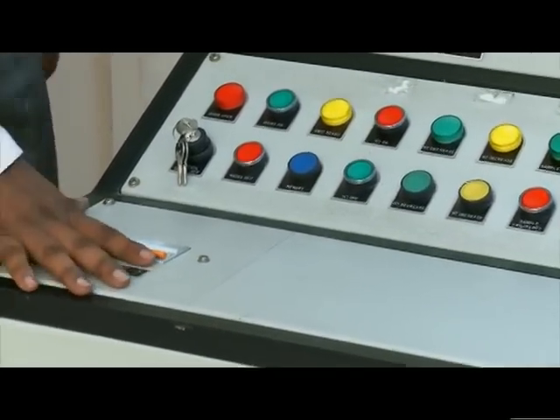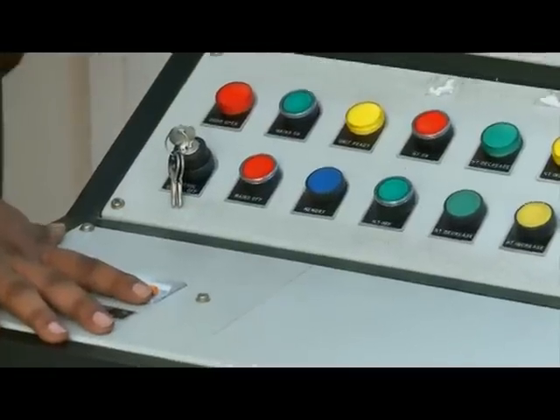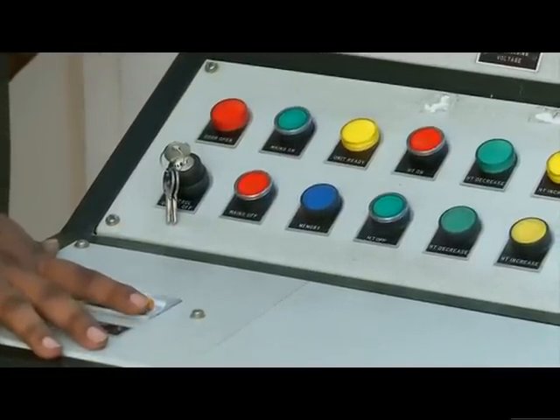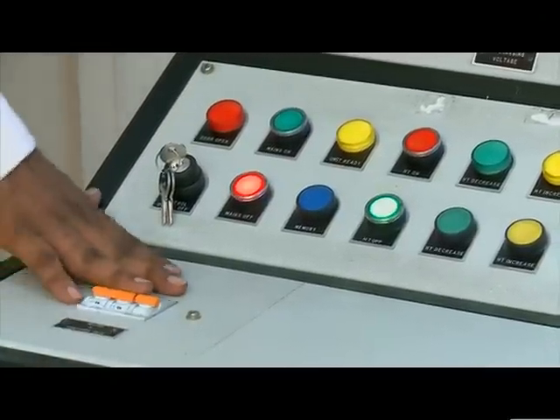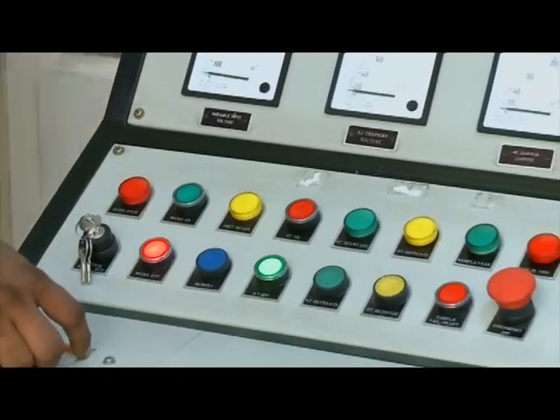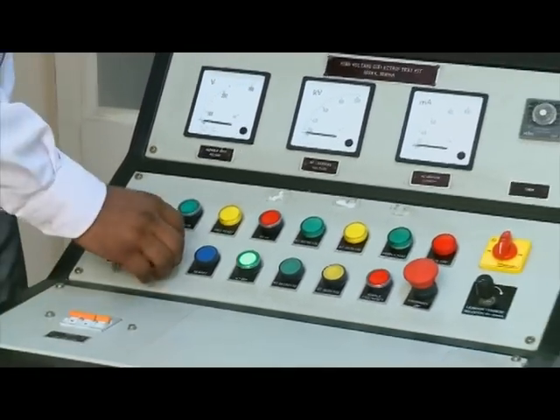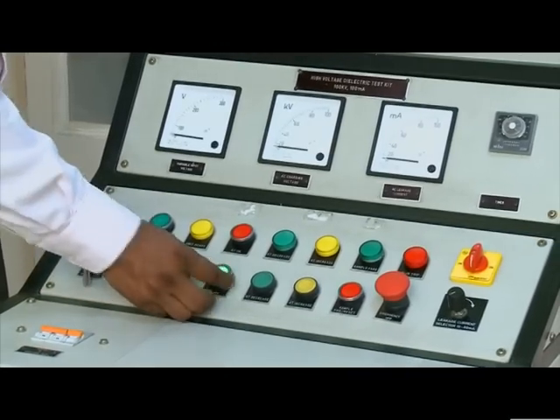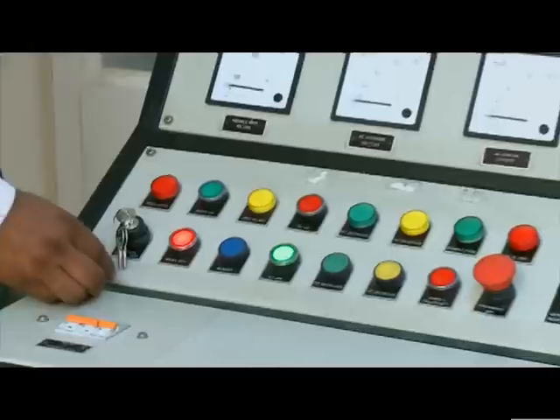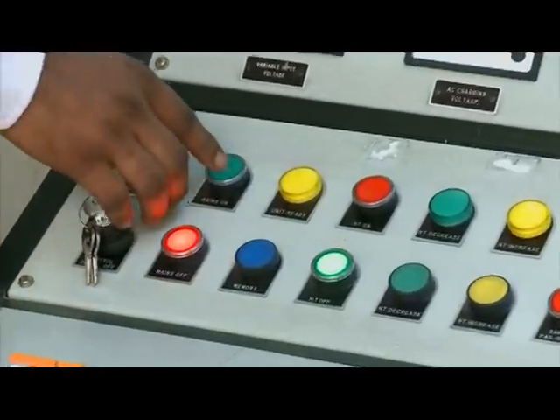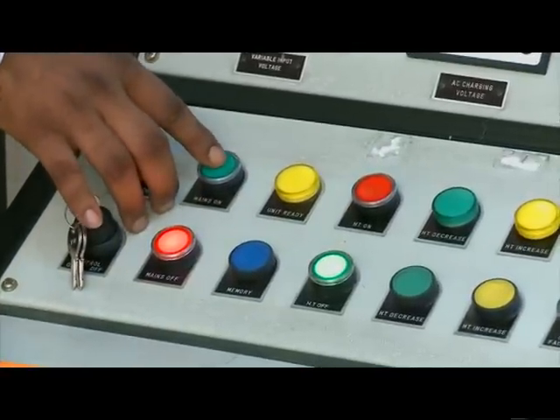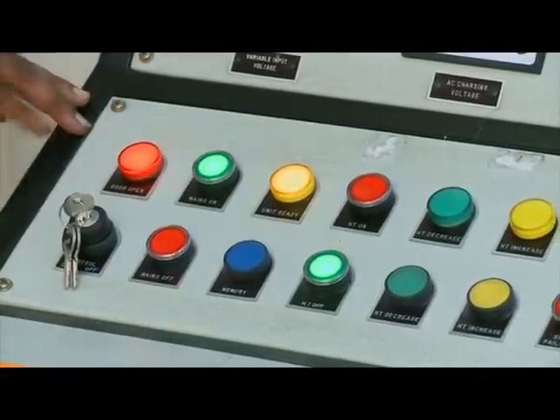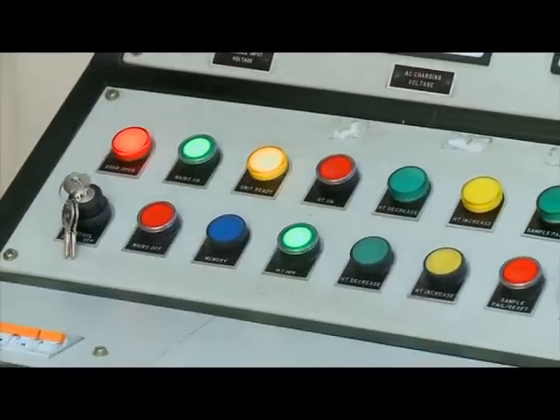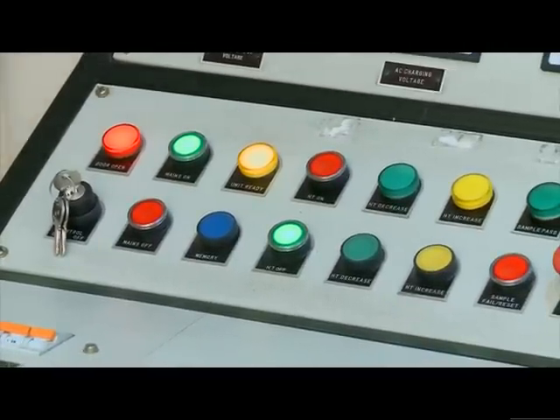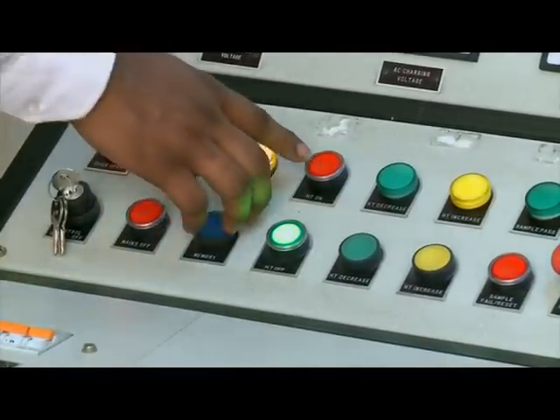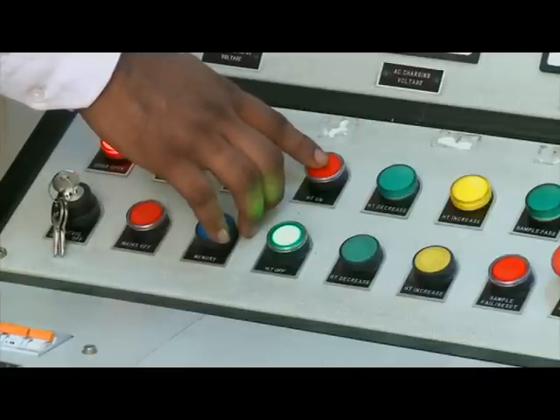With the help of this key we can switch on the system, and after that there is an MCB panel. With the help of this MCB panel we can switch on the supply to the control panel. When we put these MCBs in the on condition, the mains off and HT off indicators will glow. After that, we have to push the mains on button, which indicates that the supply will continue to the control panel. After that, we will switch on the HT.